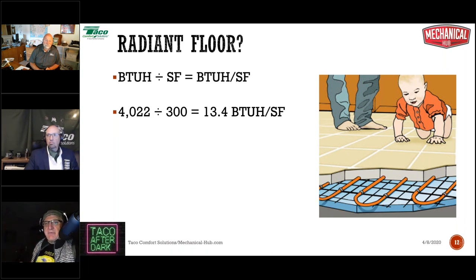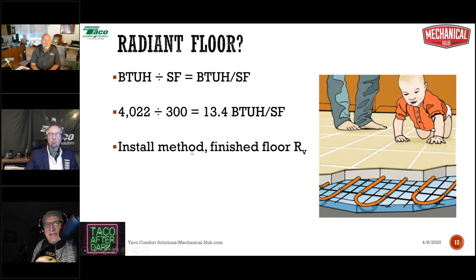Now, here's another thing about radiant floor heating. Radiant floor heating gives off heat based exclusively on its surface temperature. It's a radiant heater, it's a radiator. So it gives off heat based exclusively on its surface temperature. The warmer the surface of the floor, the more BTUs per square foot it will give off. Remember that, that's going to be important in a minute.